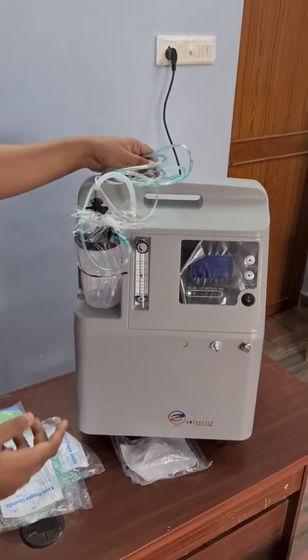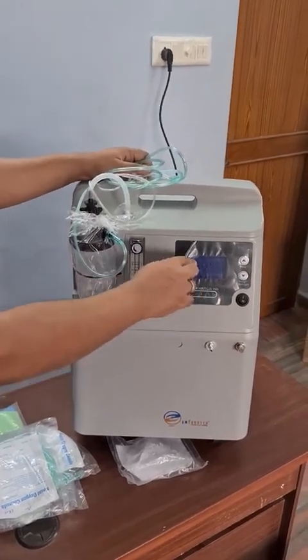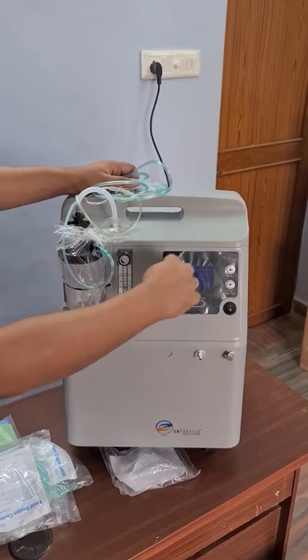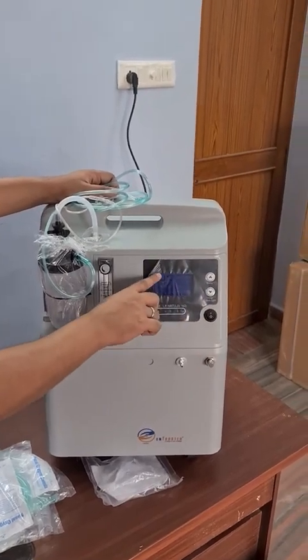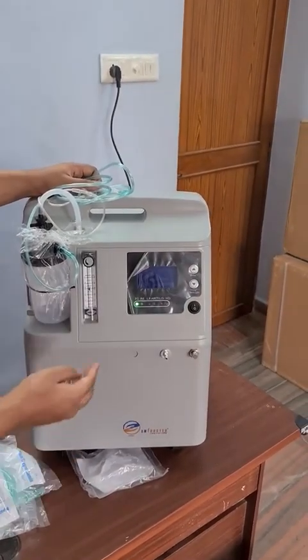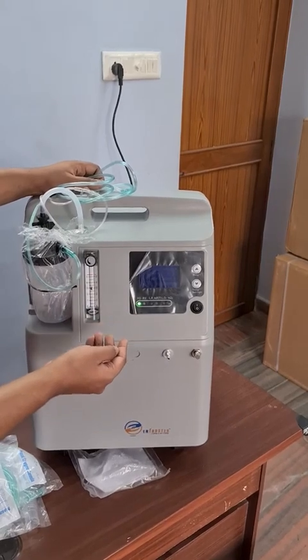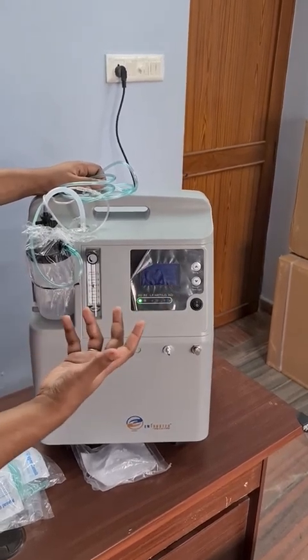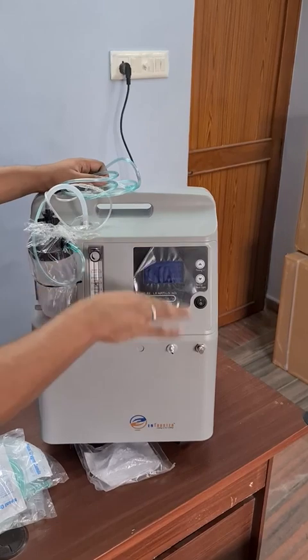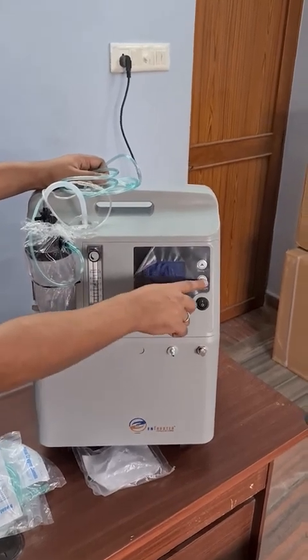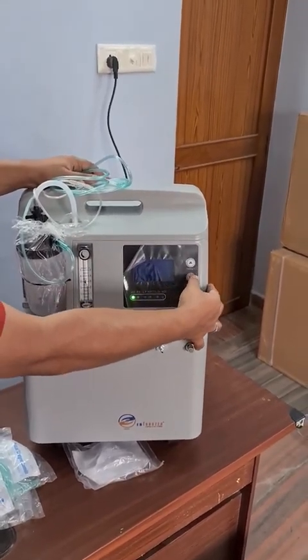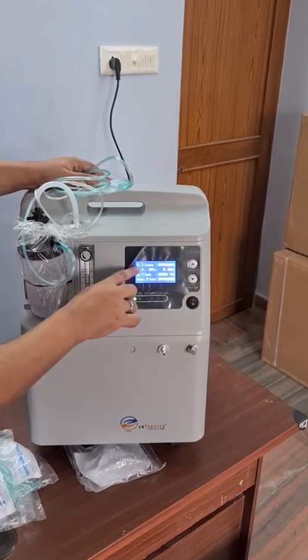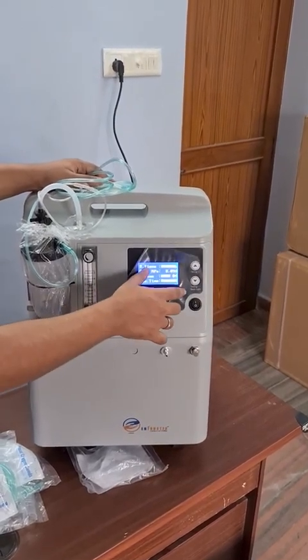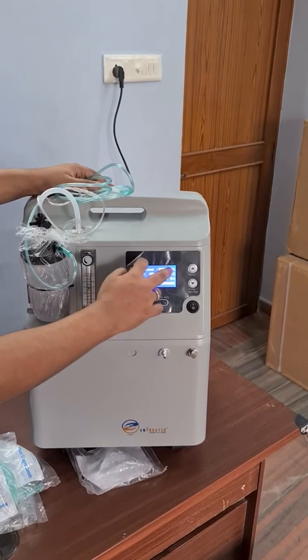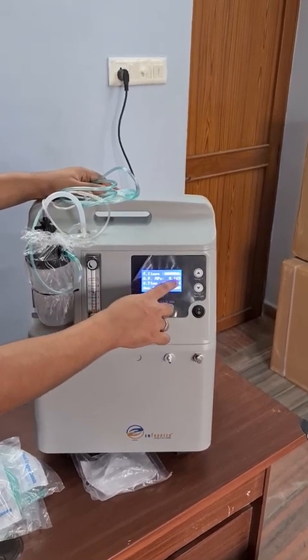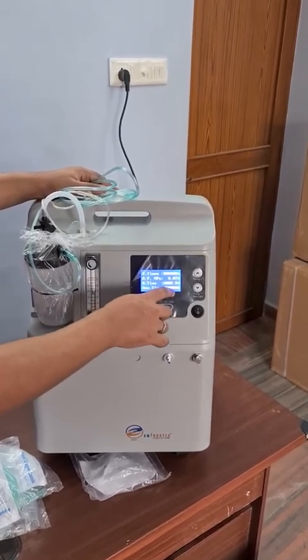Now I will tell you about the alarms in detail. As you can see, once we switch on, after some time the display goes blank. This is like an auto saver function, because you are not going to get any required output from the display. If you still want to see the display, press this down button 2 times. The second time, it will switch on again. You will just see the switch time, the output pressure, operation time and accumulation time.